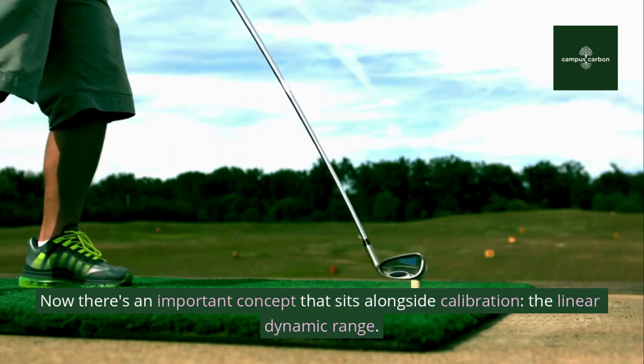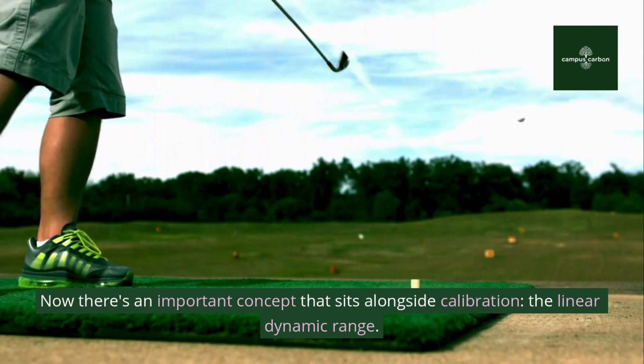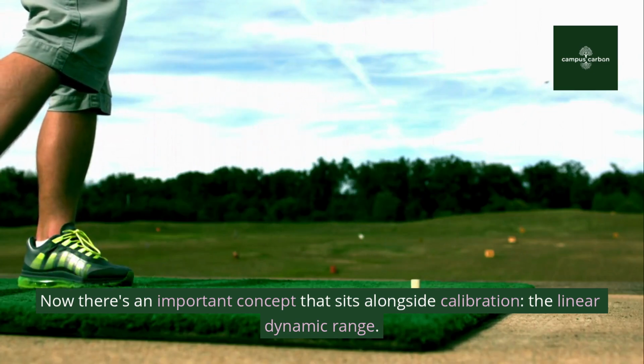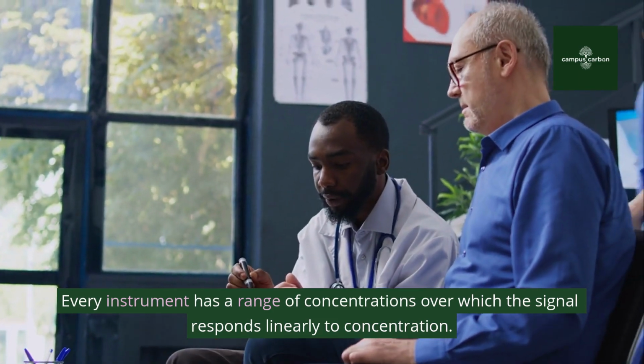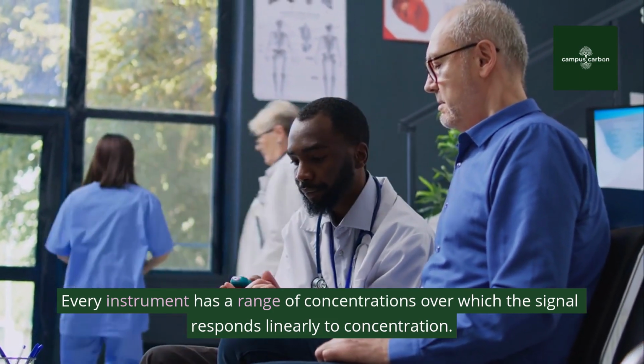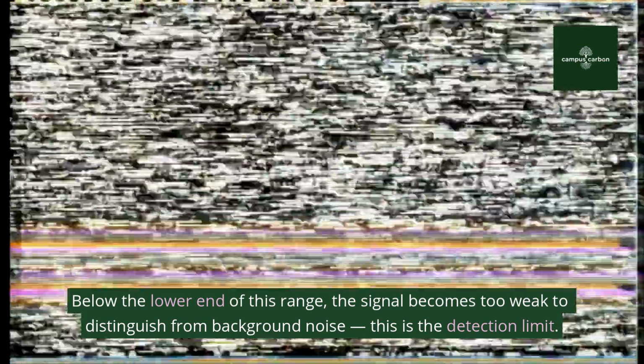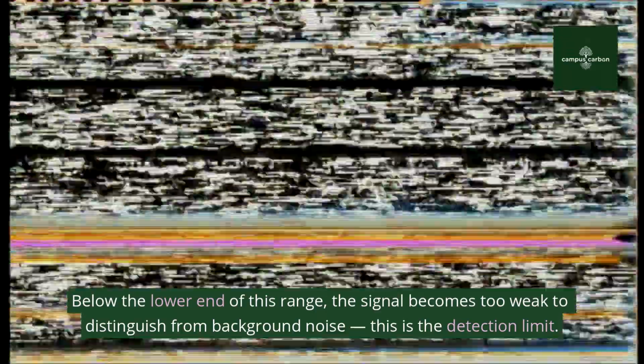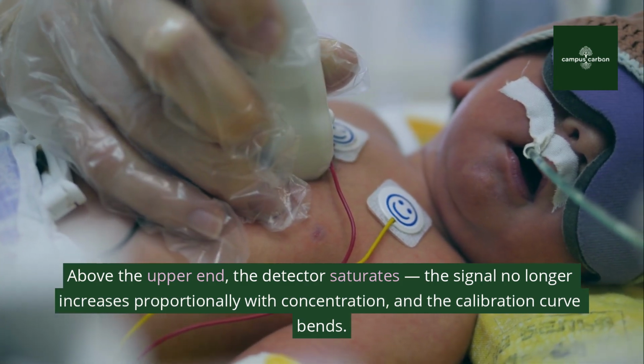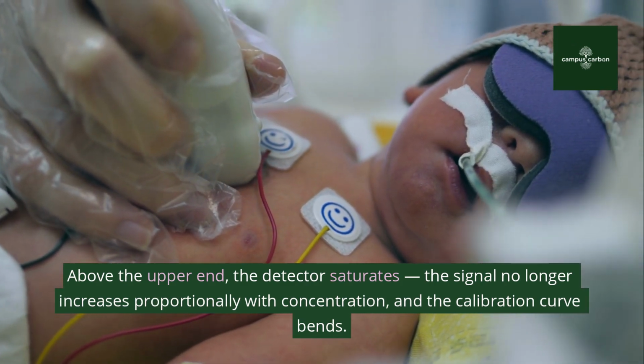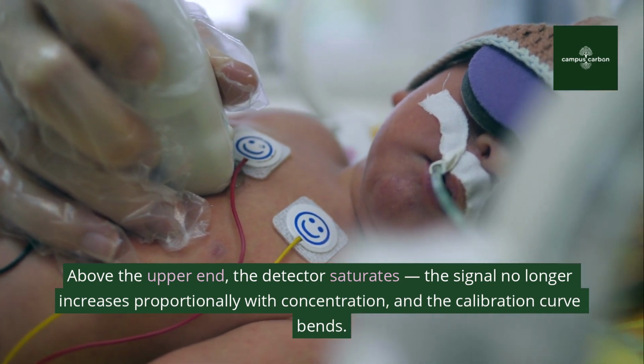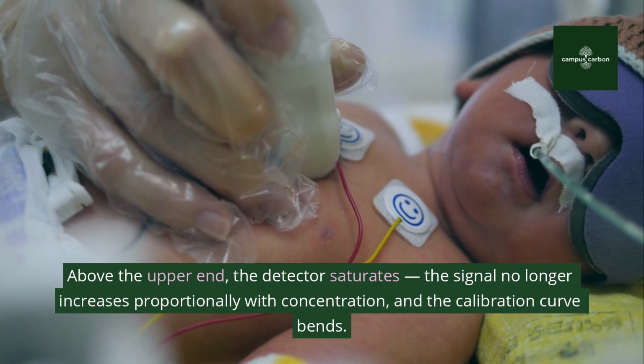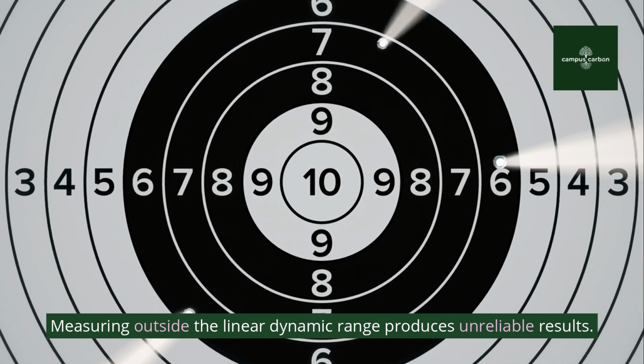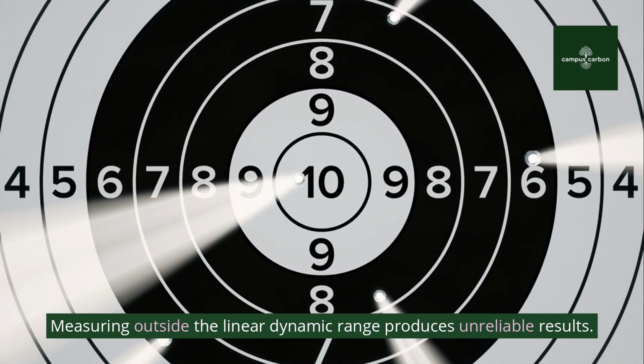Now there's an important concept that sits alongside calibration: the linear dynamic range. Every instrument has a range of concentrations over which the signal responds linearly to concentration. Below the lower end of this range, the signal becomes too weak to distinguish from background noise. This is the detection limit. Above the upper end, the detector saturates, the signal no longer increases proportionally with concentration, and the calibration curve bends. Measuring outside the linear dynamic range produces unreliable results.